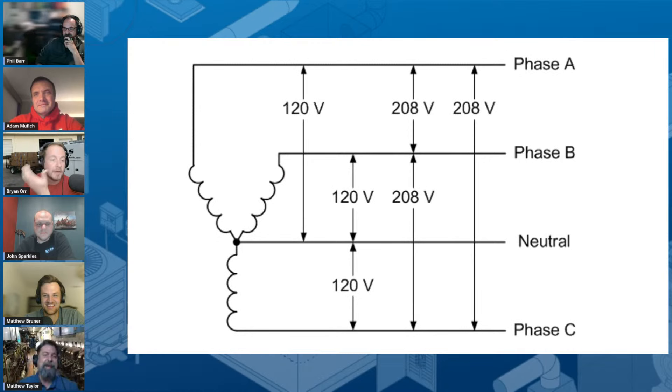The load balancing point is important — that's actually a bigger and more important reason, especially in buildings that have motors. As electricians, we're not just wiring AC equipment; we're wiring outlets and lights throughout the whole building. If we wire the whole building without considering load balance, we're going to have more voltage drop on A phase versus C phase, and that's in turn going to affect all the motor loads. And somebody you may know made a good app that will do all that math for you.